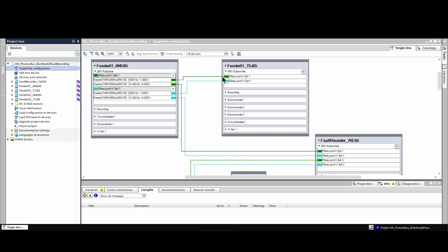This is for providing sampled measured values to the protection relay. The 14.4 kHz stream of the merging unit is connected directly to the 7KE85 fault recorder. The more detailed stream is connected to the fault recorder, and the 4 kHz stream is between the merging units and the protection relay. The same procedure takes place for feeder number 2.